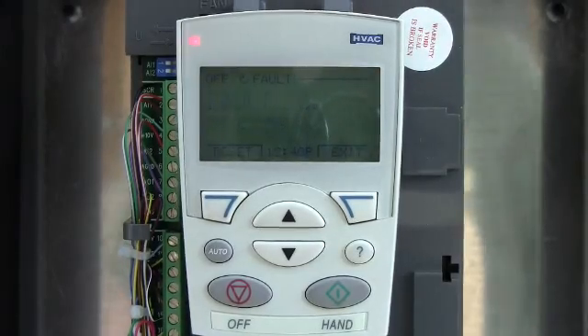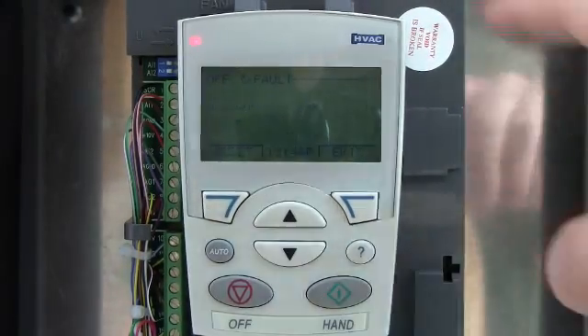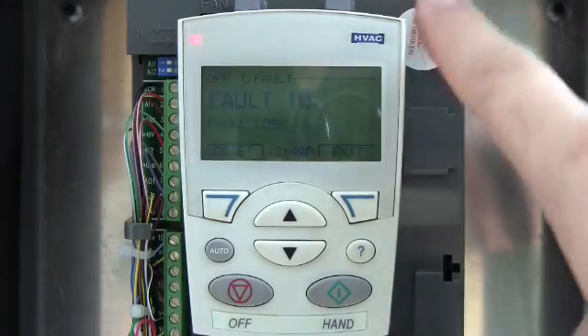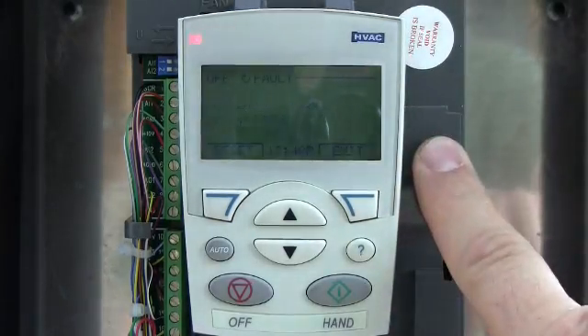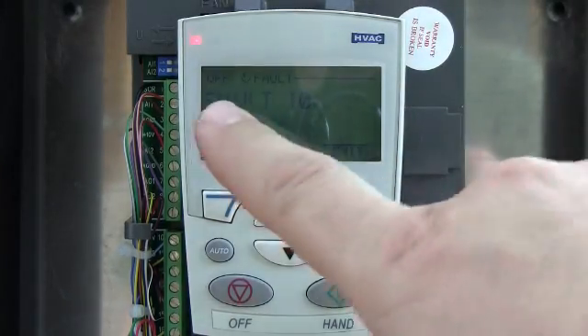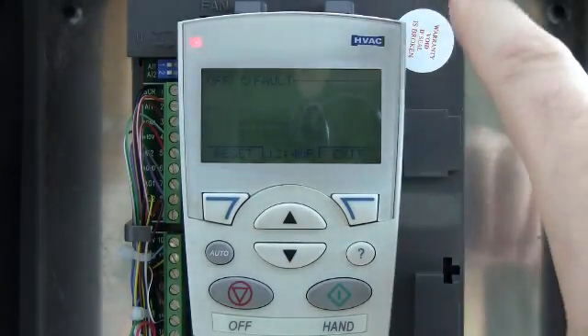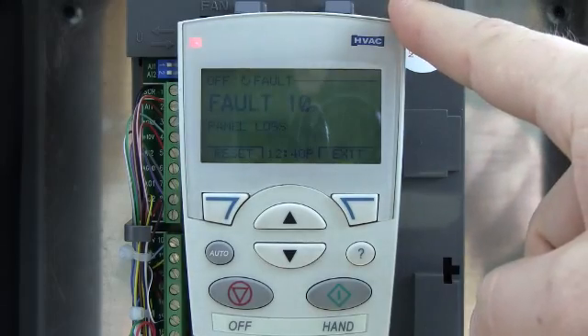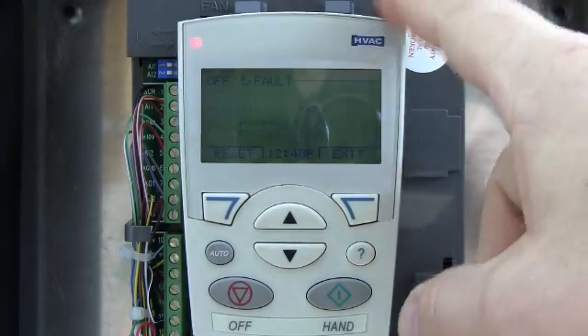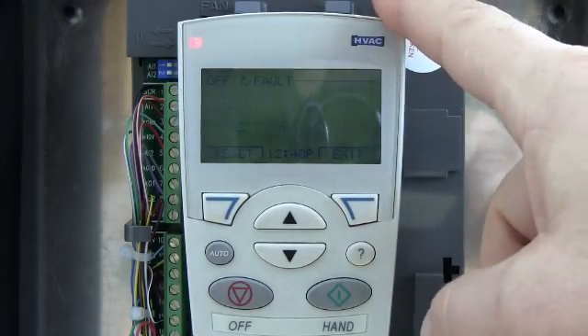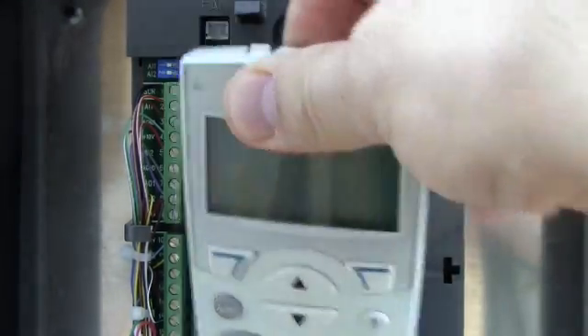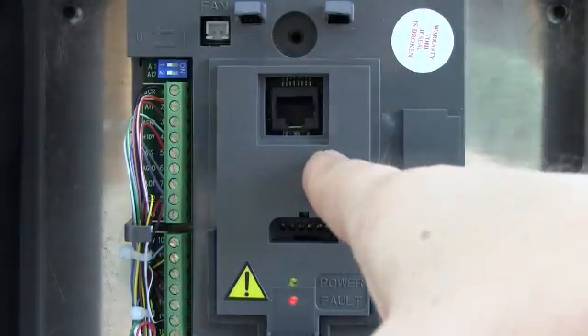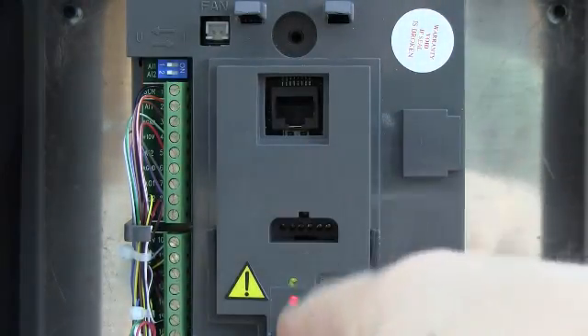Hi, this is Mark with NHA again. This is an ABB ACH 550 series drive. Another common question I get is fault 10. Simply put, that is panel loss — what the drive is saying is panel loss. That means the drive lost communication between the keypad and the main control board.